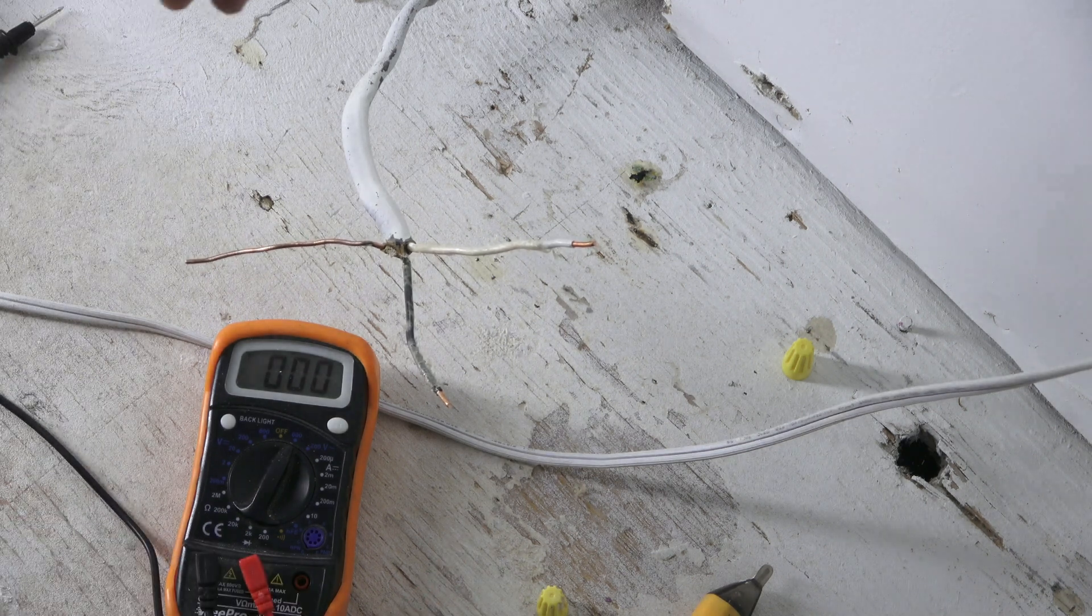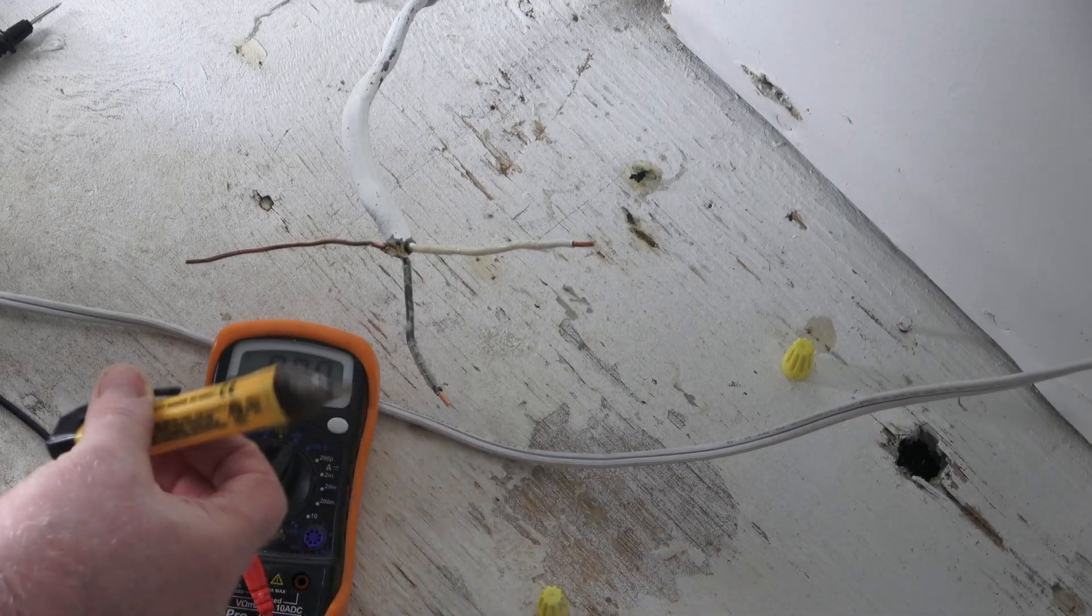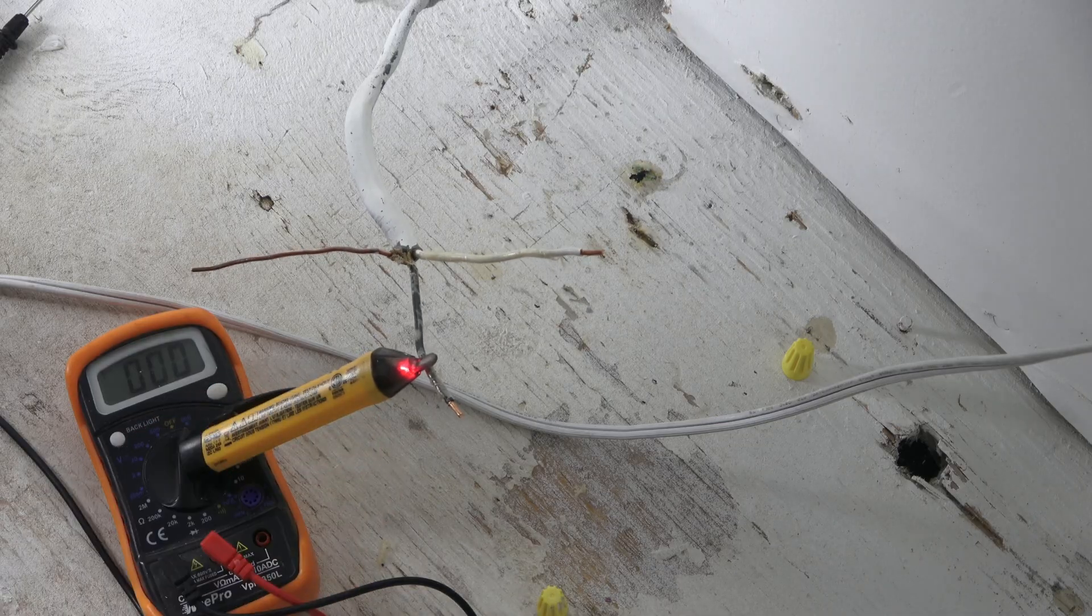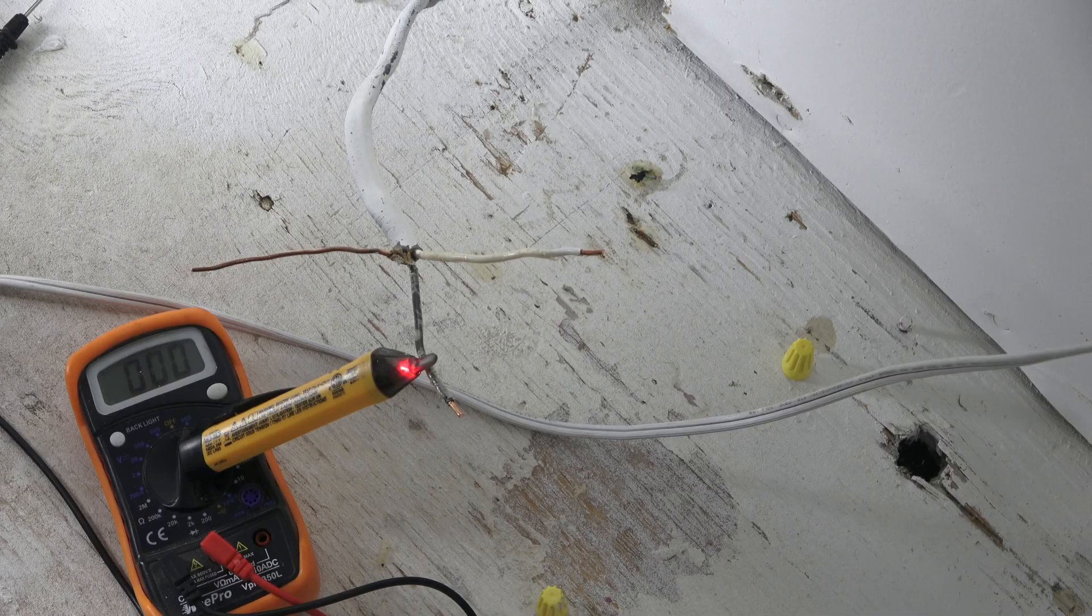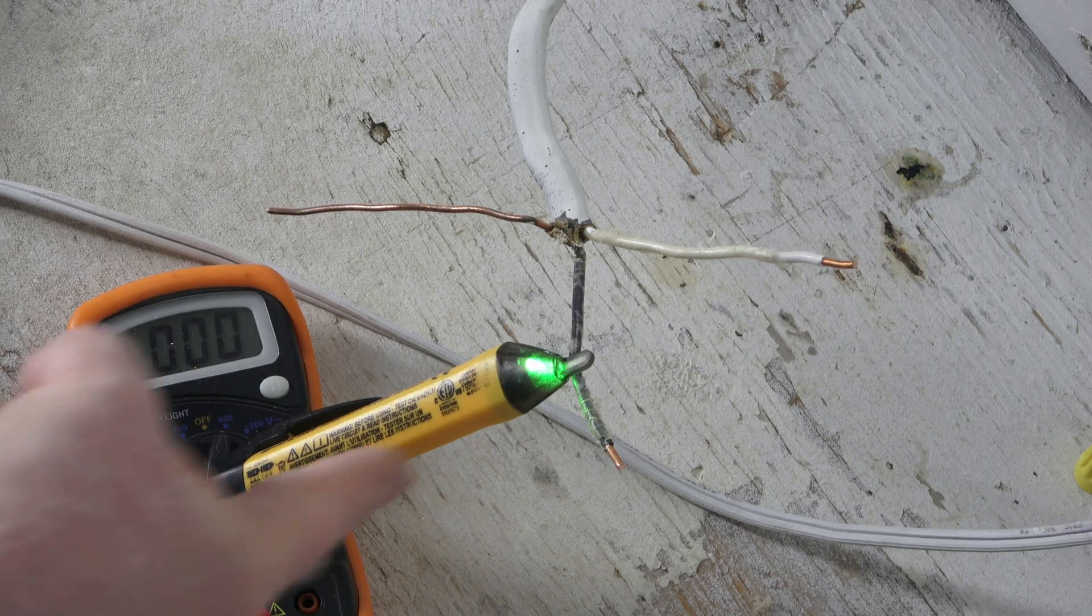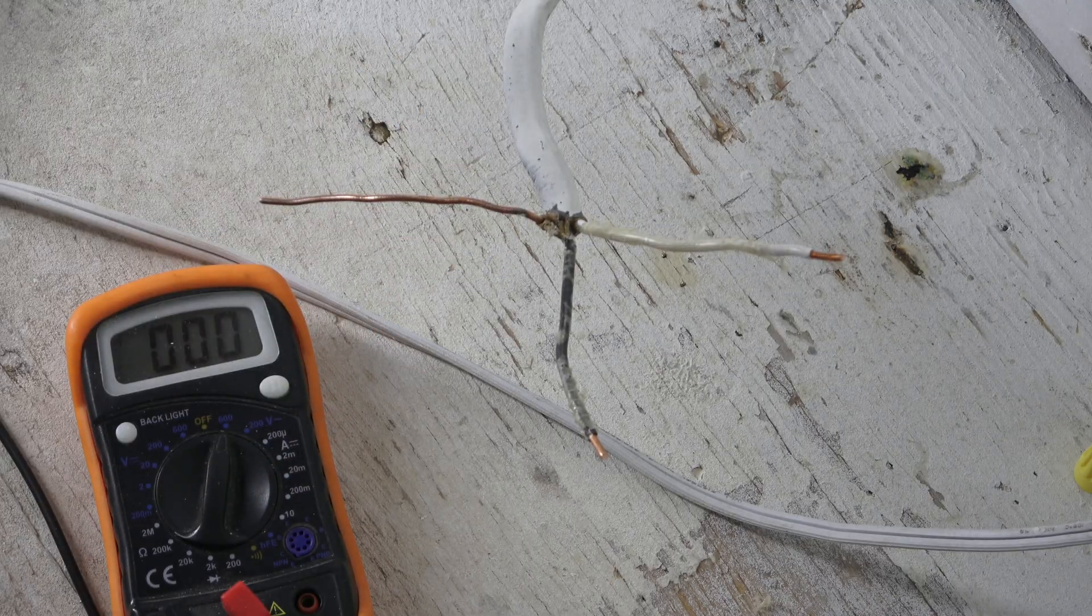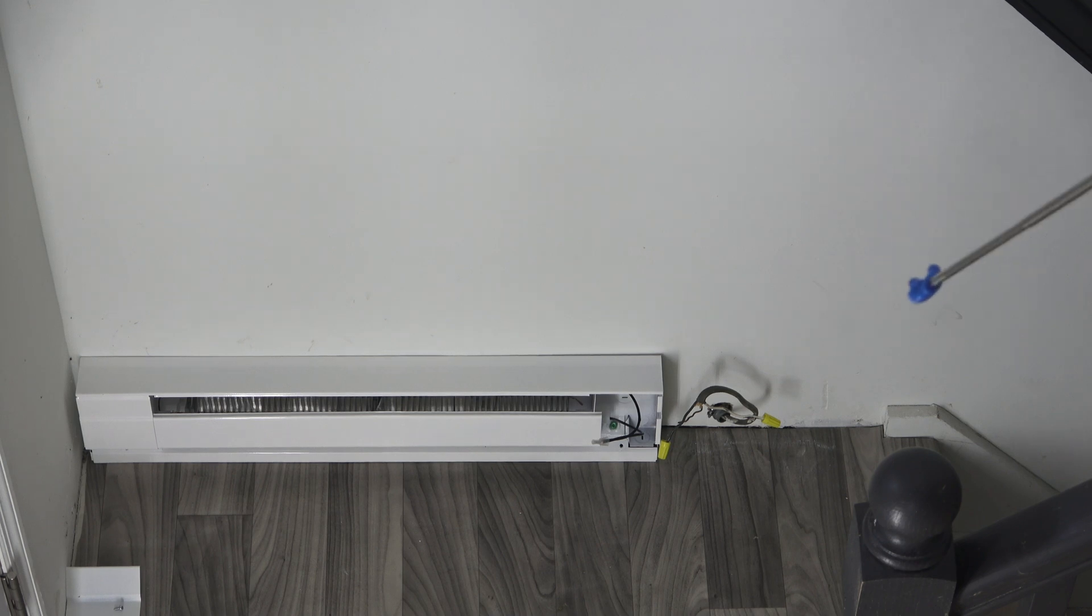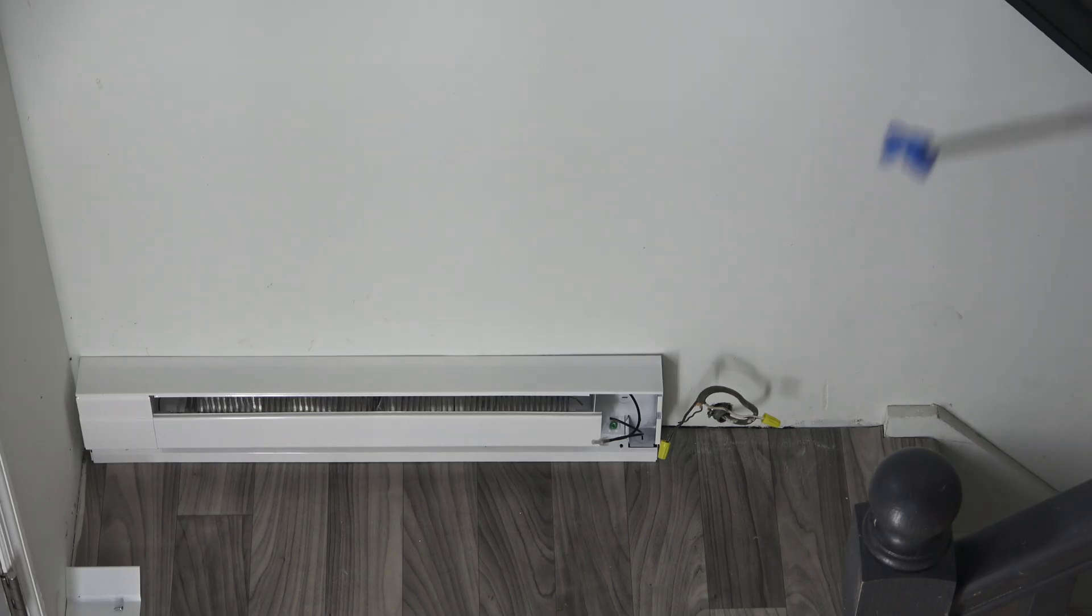So now we want to find a breaker in the panel and kill power. So what I do is use the tester, lean in on here, go down and start tripping breakers until that sound goes out. Power off. Now we're ready to make the connection to the baseboard. I also like to note that lower unit is also operated by the same wall thermostat, and you can do all electrical tests to that unit, as I just showed. And I have the breaker off. It's all the same circuit. So there's no power here or up top. So we're ready to mount both units.